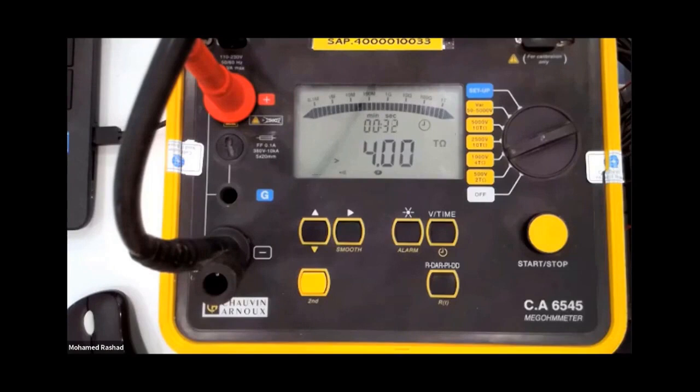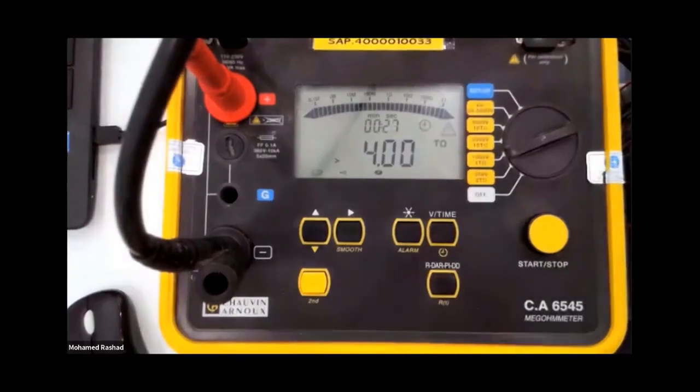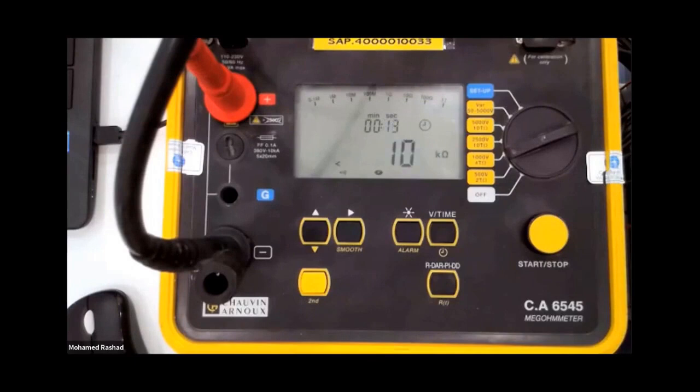All right, come here while it's working. I will demonstrate for you as if I'm removing my clamp and touching them to the ground, as if something happened during the injection. Look, you will immediately see what the device does. The device will immediately show you that the resistance is less than 10 kilo ohms, and will stop its injection.